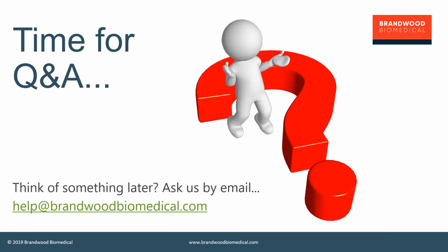So does that mean that you have to do chemical characterization? Well, maybe not. What does your specification say? If your specification says that it needs to be made out of 316L stainless steel, then it may be adequate for you to get the certificate of analysis for that lot of stainless steel that was supplied to your manufacturing centre and check that it does in fact meet the specification requirements for that alloy, and then you're done.